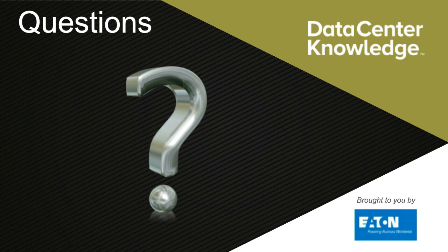Well, that's a good question, and the answer is a positive one. If I'm using a traditional UPS battery with 5 or 10 minutes of battery backup, for example, my lithium battery is going to be, for the same backup time, dramatically smaller and lighter. So that also allows the capability of saying, instead of retrofitting with another 10-minute battery, maybe I could put a 30-minute lithium battery in the same physical space without having to build anything out. And that now opens the door to my ability to participate, at least short term, in these kind of energy management initiatives we've been talking about today. So a lithium battery is going to give you some advantages in footprint.